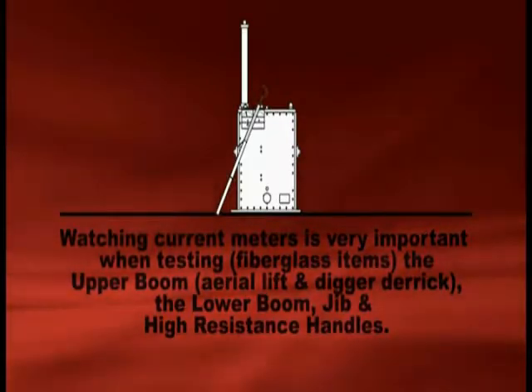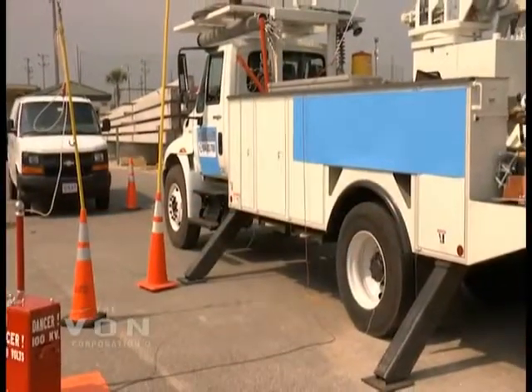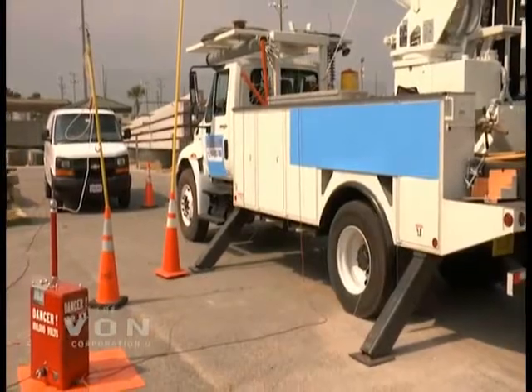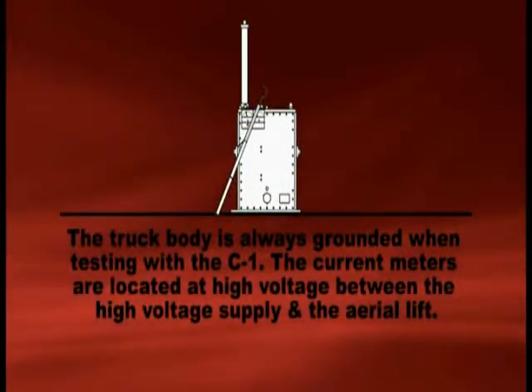When testing the aerial devices with DC, it is not necessary to put the boom in any particular position. It will not affect the test as long as you keep the insulating section a minimum of 18 inches away from your ground conductors.